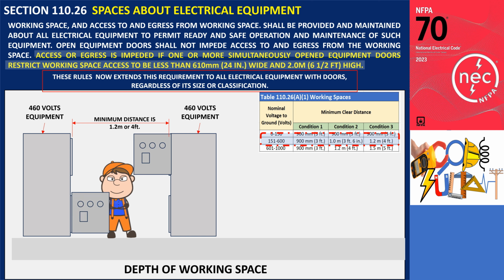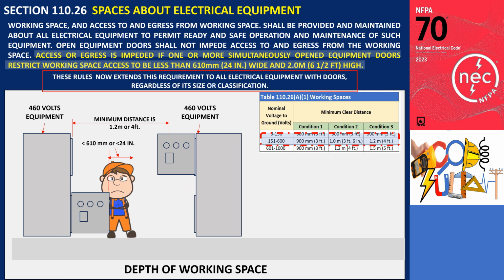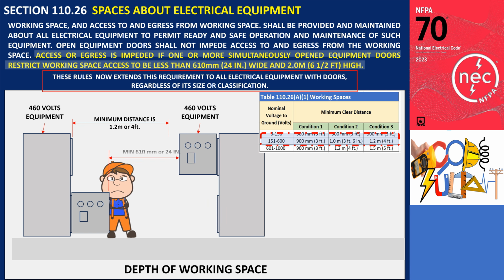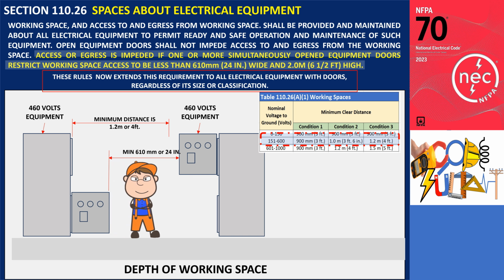However, when both equipment doors are open simultaneously, the distance between them is less than 610 millimeters or 24 inches. Consequently, this spacing does not comply with the code. As per the regulations, there must be a minimum of 610 millimeters or 24 inches of access or egress when both doors of the electrical equipment are open.